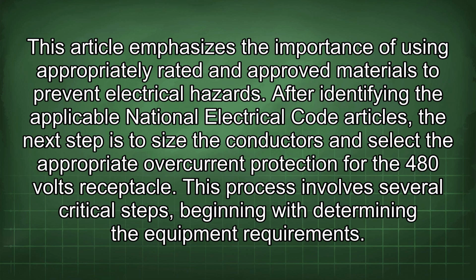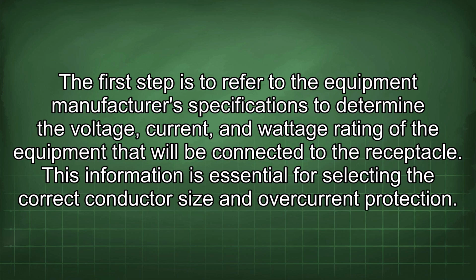After identifying the applicable National Electrical Code articles, the next step is to size the conductors and select the appropriate overcurrent protection for the 480 volts receptacle. This process involves several critical steps, beginning with determining the equipment requirements. The first step is to refer to the equipment manufacturer's specifications to determine the voltage, current, and wattage rating of the equipment that will be connected to the receptacle. This information is essential for selecting the correct conductor size and overcurrent protection.